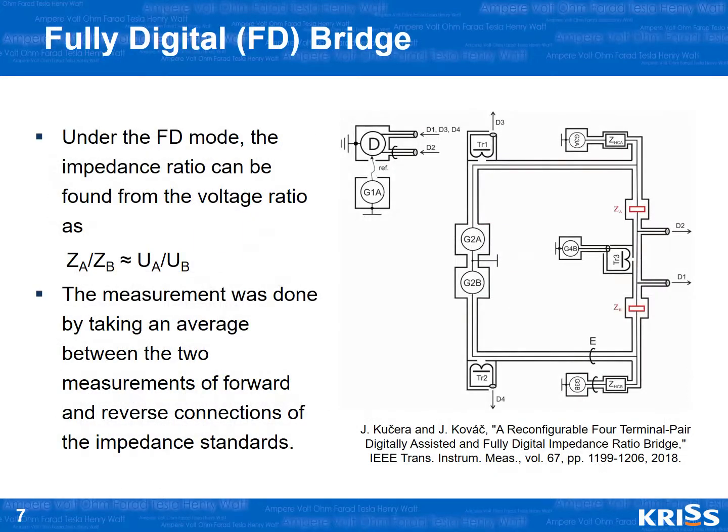Fully digital bridge. The digital bridge employed in the experiment is developed by the Czech Metrology Institute, the CMI, and it can be reconfigured in either digital assisted or fully digital mode. The bridge has been mainly evaluated in the digital assisted mode in previous studies, so in this work we will focus on the fully digital mode. The schematic of the fully digital bridge is shown in the figure.